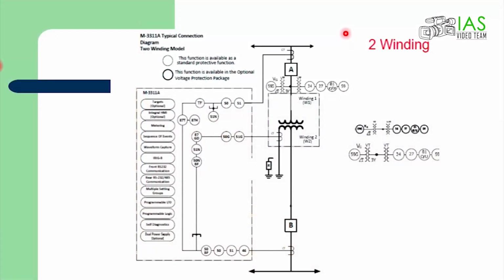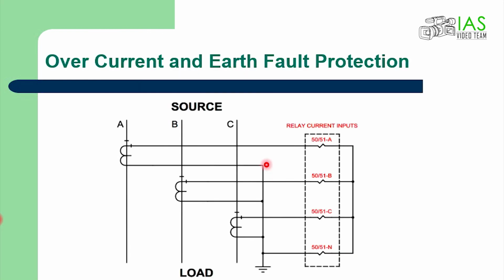Now, here a transformer is shown and protection functions are given here, right? And with this one, 50G and 51G and 87, now these are standby earth fault, 50G and 51G, right? And 87 is differential, right? Breaker failure and so on. And this 87L is also differential. Like that, there are so many protection functions marked over here. We'll go to a few of the protection functions. Overcurrent and earth fault protection.